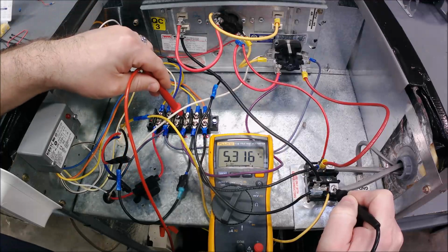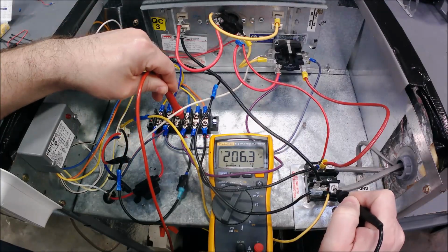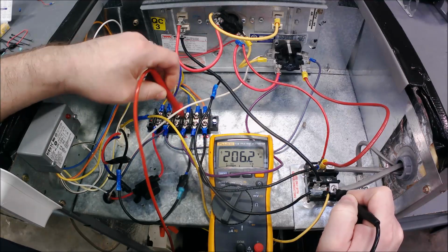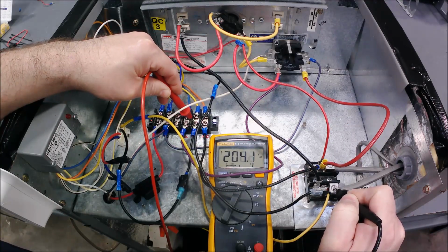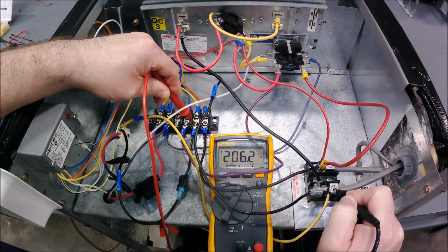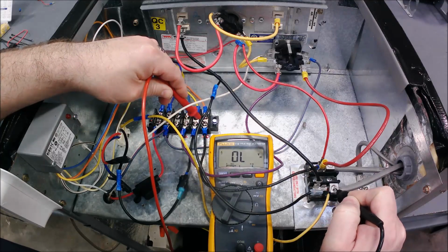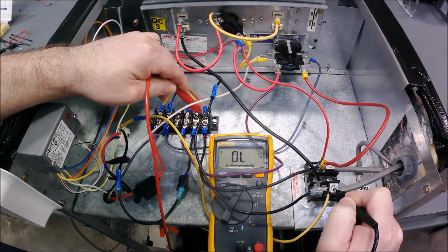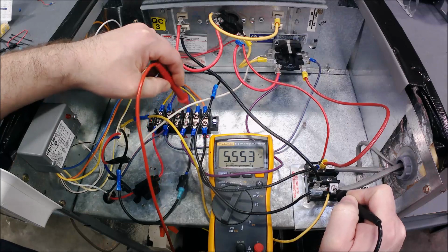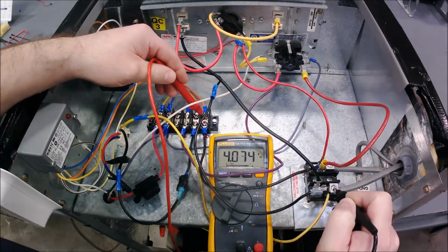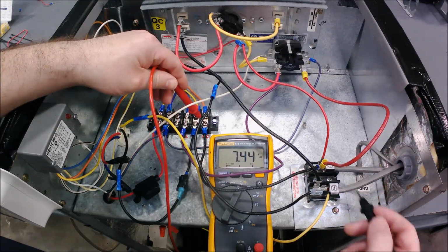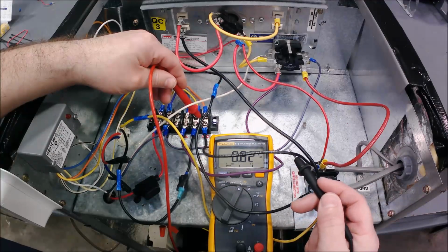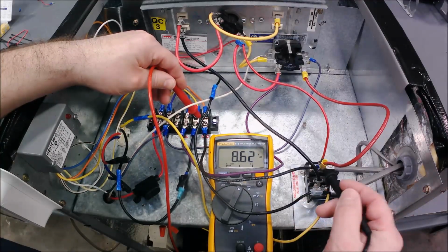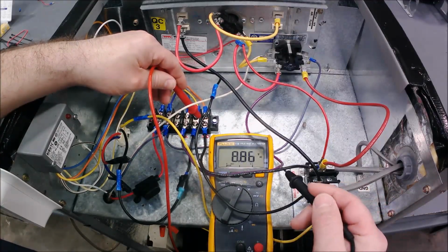Alright, look at what happens with the purple. I've got 208 as well, or 206, and of course my common's going to have 208, 206, something like that. So basically all three of these right now will read power, because they're all actually touching L1. The normally open has L1 coming from the terminal block right here on that wire, so I'm just on the opposite end of where the wire connects.